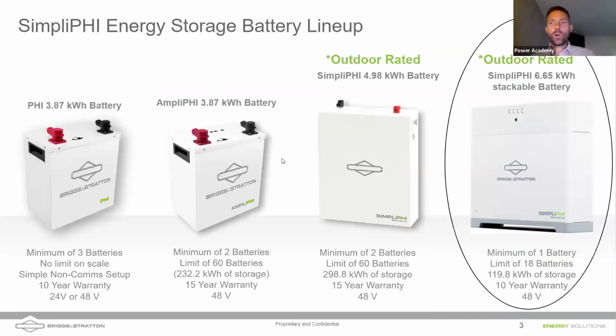So our latest battery offering is shown on the right side of the screen. That's a SimpliPhi 6.6 stackable battery. You can build stacks of that battery up to 3 tall, up to 6 stacks in parallel to get 120 kilowatt hours of backup. That's an outdoor rated battery. Temperature range charging from 14 degrees Fahrenheit all the way up to 120, I believe, Fahrenheit. Discharging range is even wider from 0 Fahrenheit all the way up to 140, I believe. So that's an outdoor rated battery. It can be wall mounted or floor mounted, and we'll talk about that a little bit.